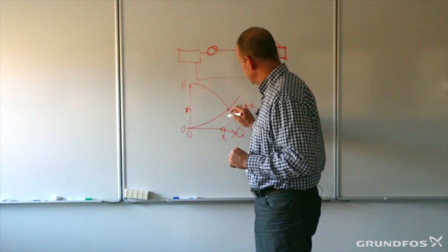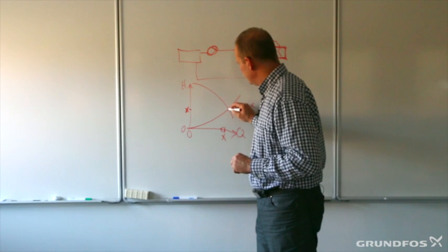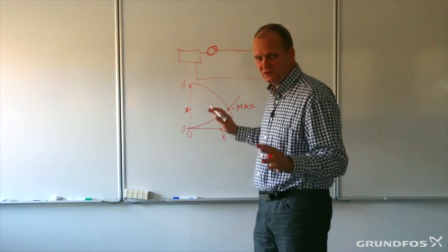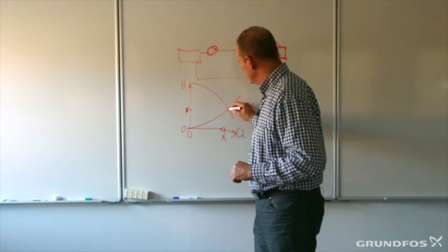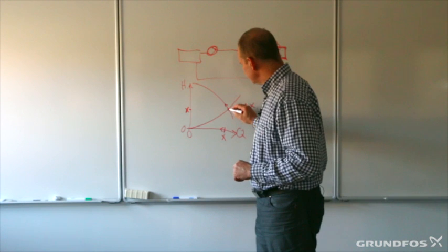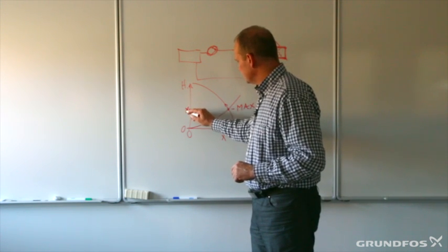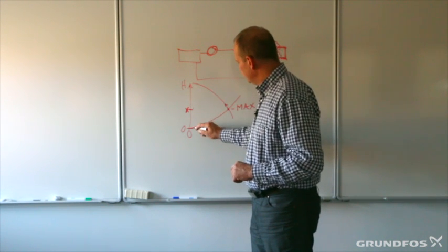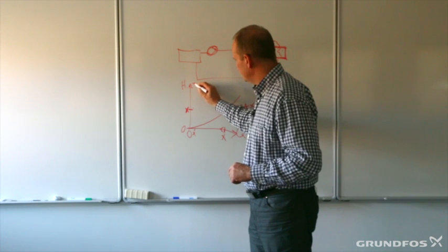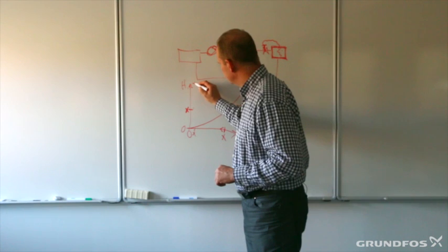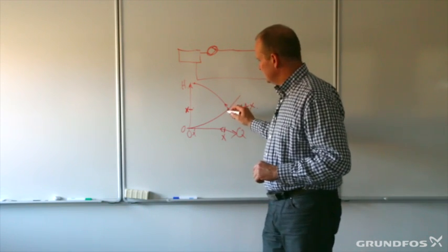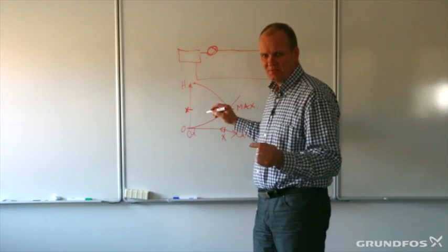But what is happening is that when the valves are closing and we have a pump which is operating at the same rounds per minute, the fixed speed all the time, the only thing the pump can do is to start to increase the pressure as the flow goes down. So this was what we needed in terms of pressure at maximum load. But when the flow need is at minimum, actually a normal pump, a fixed speed pump, will deliver this much differential head.